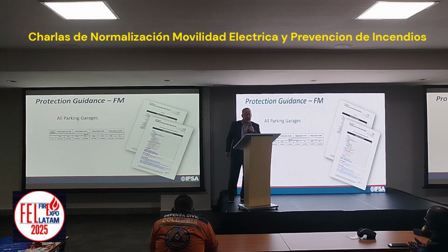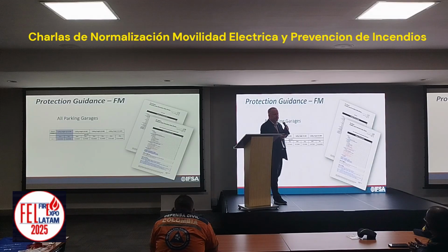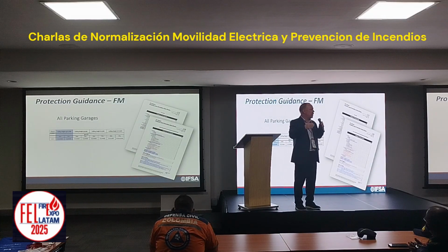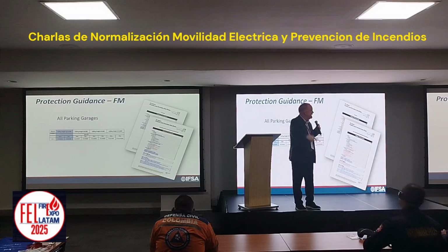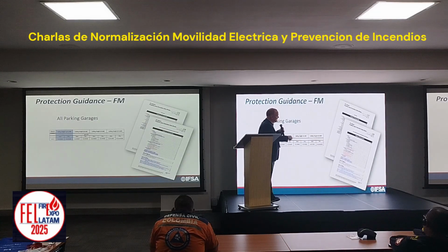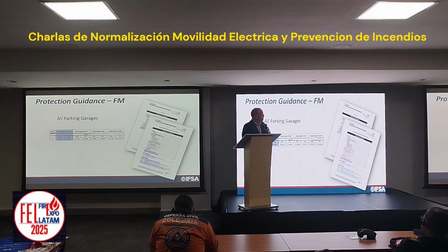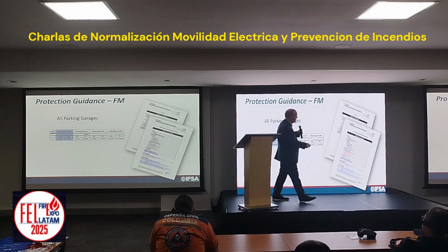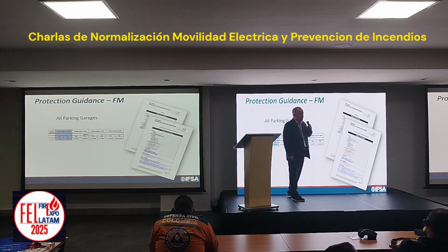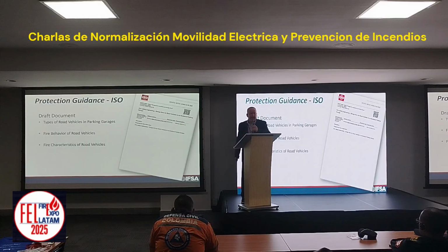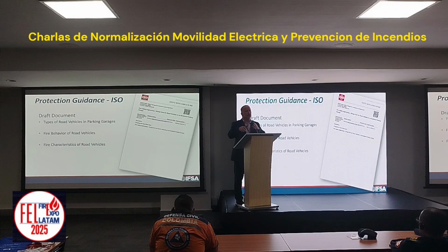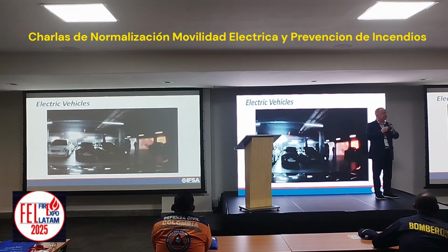Factory Mutual also contains guidance for these, but it's pretty much based on the height of the racking. You can have car stackers up to 4 levels or more, and depending on the height of the ceiling, we have a different design parameter based on documents 7-15 and 3-26 on non-storage occupancies. ISO, the International Standards Organization, is also looking into this, and has a document stating you need protection in these spaces.